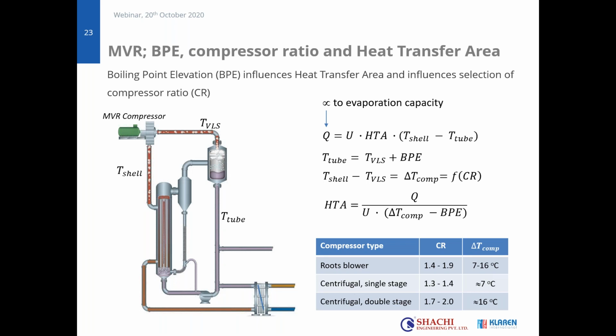If you look at centrifugal compressors, this compressor ratio is more limited for a single stage. And that has to do with the performance of such a single blade system. And typically, this would have a compressor ratio of between 1.3 and 1.4 for a single stage. So that means if you're offered an MVR unit with a single stage compressor, you know that the delta T is limited to 7 degrees.